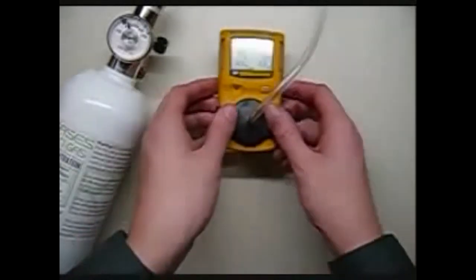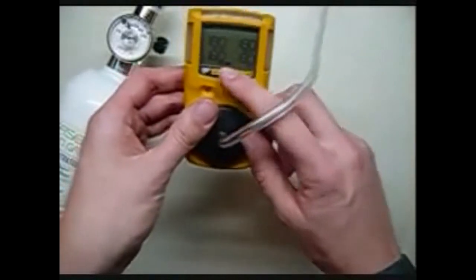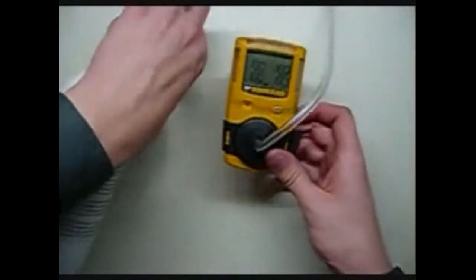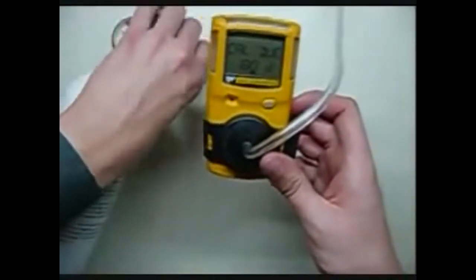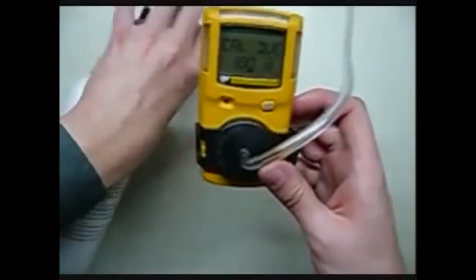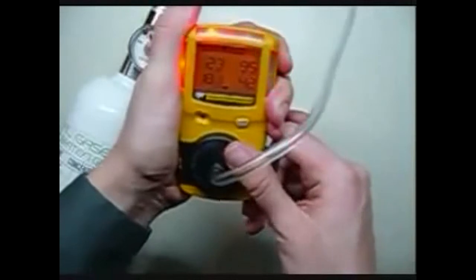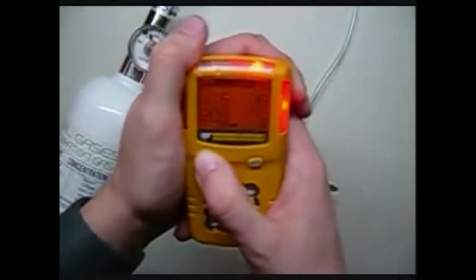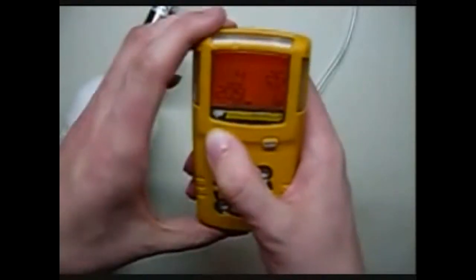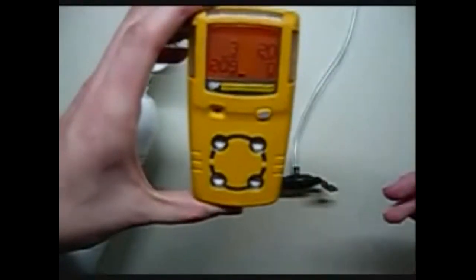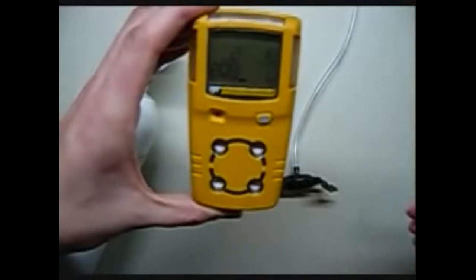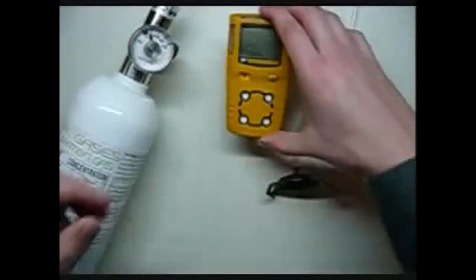Okay, now you notice the monitor's cal comes up saying 180, 180, 180. That's how many days until your next calibration. Go ahead and turn your cal gas off. Now, I disagree with VW here. You should always calibrate your monitor every 30 days by OSHA spec, and I'd bump test it every day before you go out into the field. And you should just put your thumb over the alarm, quiet it down a little bit, and we'll let it cool off.